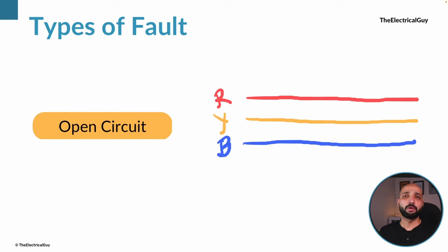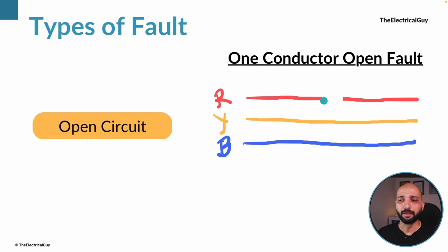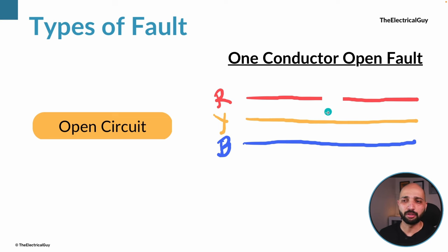Talking about open circuit — let's say we have three phases R, Y, and B, and one of the phases is broken down in between. As a result, the current will not flow beyond that point; it is stopped — it is opened. This is an open circuit fault. Here the R phase is broken down, so out of three one phase is down — this fault is called a one conductor open fault.